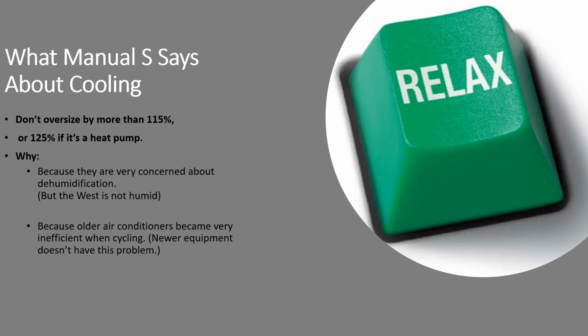What Manual S says about cooling: don't oversize by more than 115%, and no more than 125% if it's a heat pump. Why are they so worried about this? Because they're worried about dehumidification. The good news is that we don't have to worry about dehumidification in the summertime in the Northwest. If that air conditioner is running at all because it's hot, it will provide sufficient levels of dehumidification.